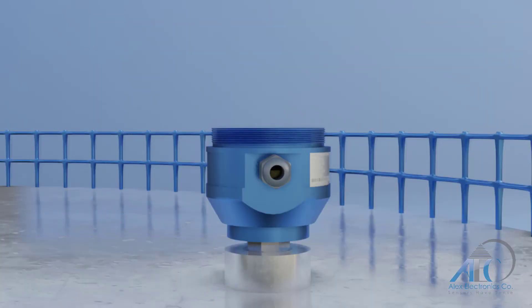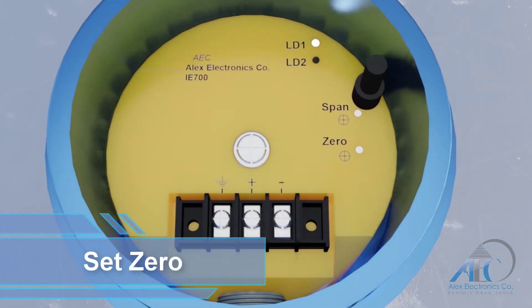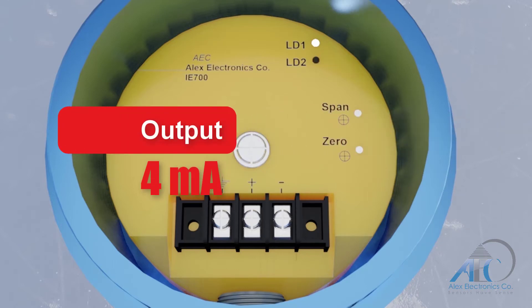To set the zero, put the magnetic pen near the zero programming circle for about three seconds until the programming LED labeled LD2 starts flashing, then remove the pen immediately. At this point the output signal is 4 milliampere.